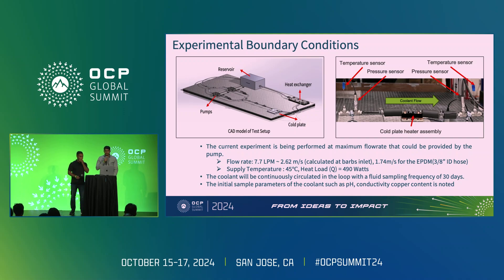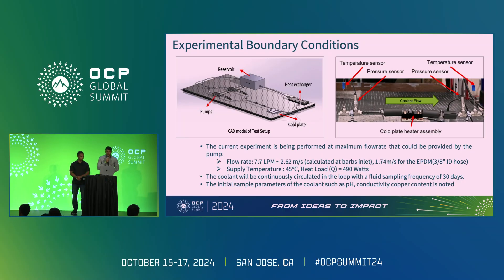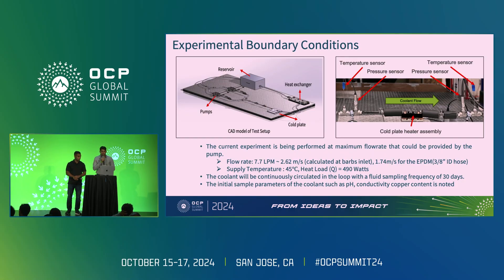Hello everyone. The experimental setup consists of a copper cold plate which is mounted onto a heater base, and it mimics a data center scenario where a cold plate is mounted onto a CPU or GPU, and heat is being carried away by the coolant going into the microfin channels. There is a heat exchanger present inside the cold loop, which is used to maintain the coolant at the desired temperature, and a reservoir to have an ample amount of samples so that we can collect samples at regular intervals to analyze the coolant. There are two pumps used for this closed loop to help circulate high flow rates of coolant through the cold plate.